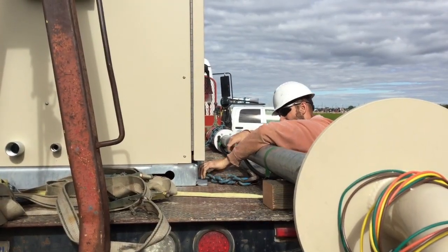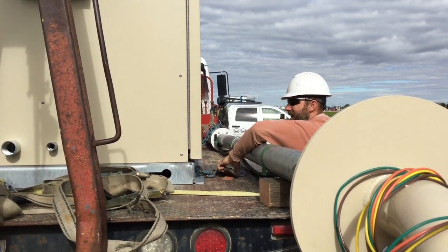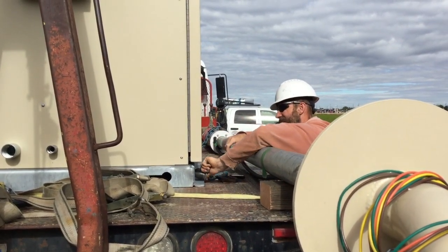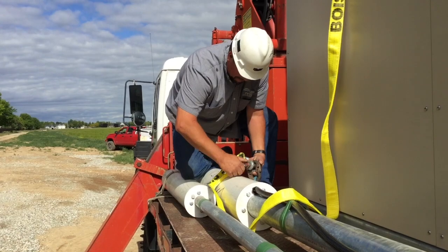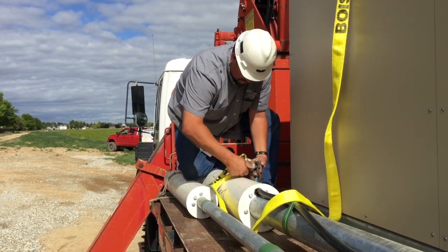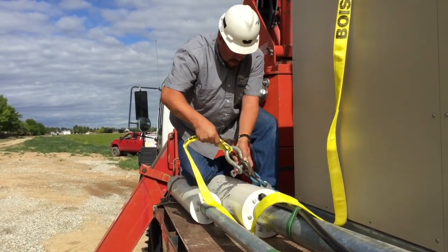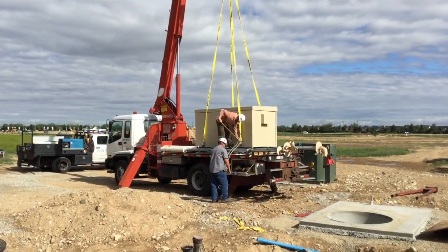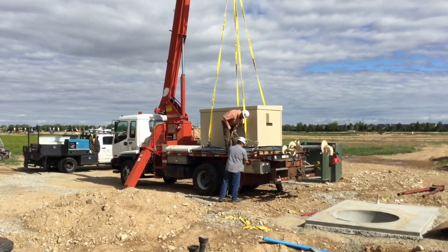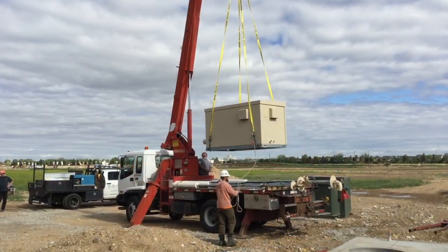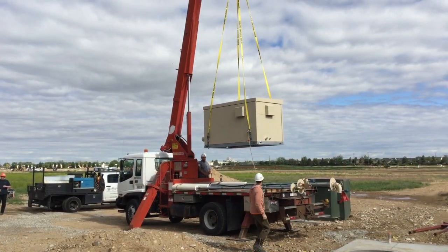Prepare the pump station for lifting by connecting hoisting chains and hooks to the station skid. Use caution to be sure nothing comes in contact with the pump station enclosure to prevent scratches or structural damage.